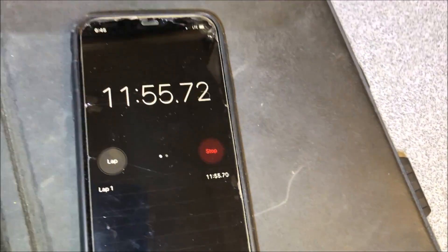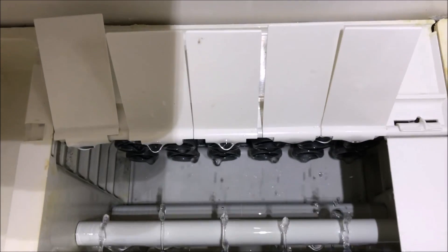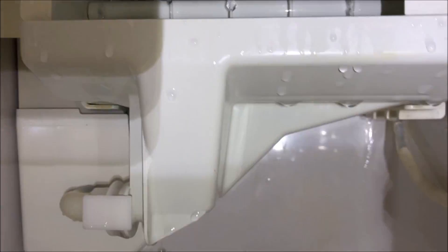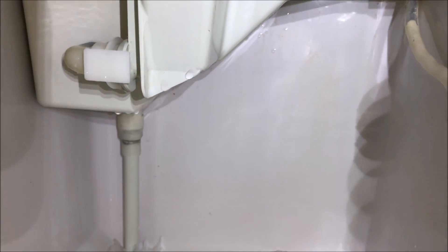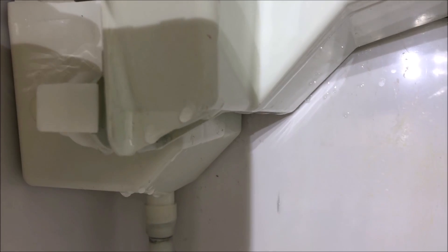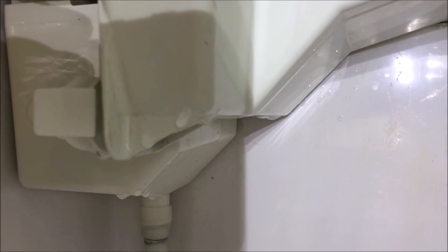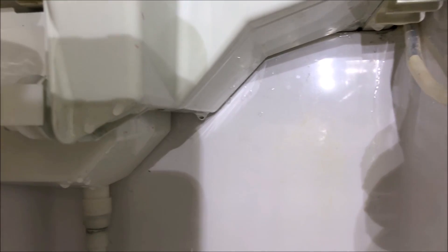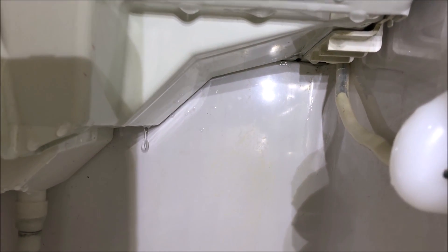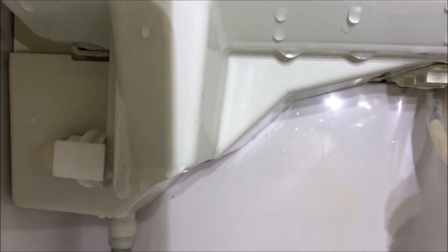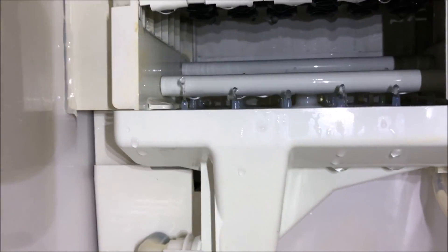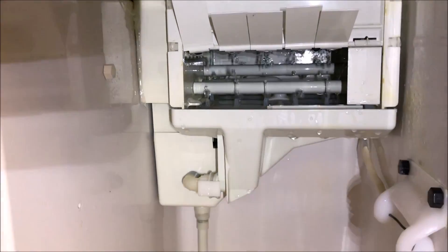Alright so look at that. Eleven, twelve minutes into the cycle and we're having the same issue again and look at that water leaking. So we're losing water. That's why the water level in the trough is dropping so low that the pump cannot pick it up anymore. We're only twelve minutes into this cycle. We're still like probably seven, eight, nine, ten minutes away from the harvest.